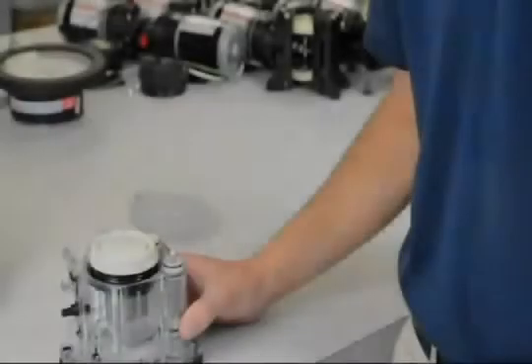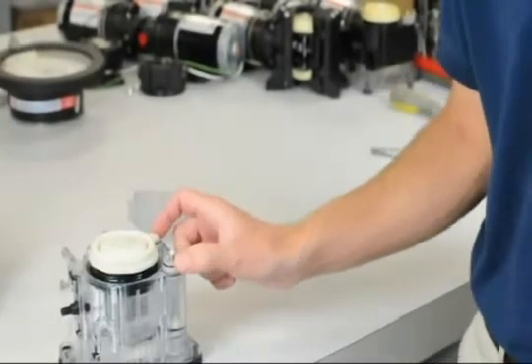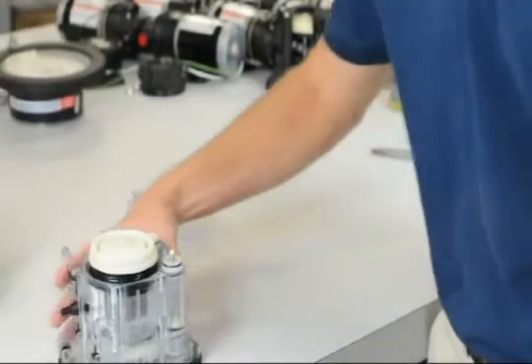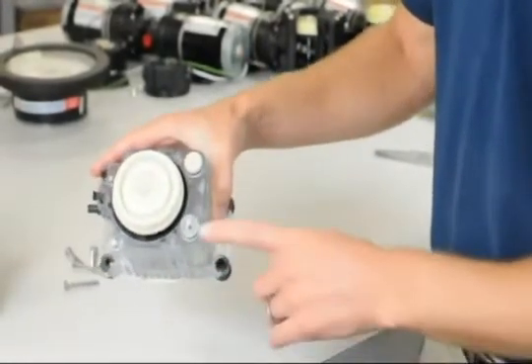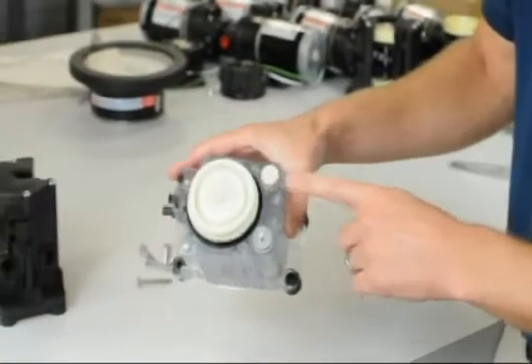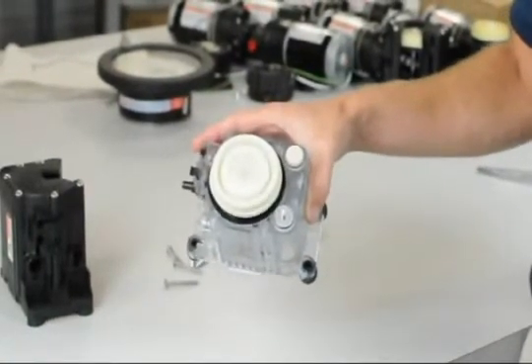Now that we've taken off the top end cap, we have access to one of the diaphragms and two of the core check valves. One thing to note before we move the check valves is that they're facing two different directions. This has to do with the function and the flow of the water inside the pump.